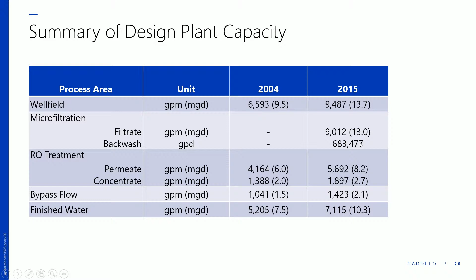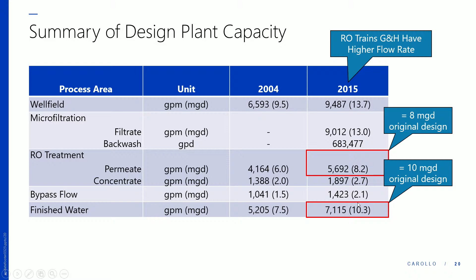And instead of a 10 million gallon per day nameplate capacity, it should actually be capable of producing 10.3 million gallons per day. But to get to that, we need 13 million gallons per day of filtrate from the microfiltration process and upwards of 13.7 million gallons per day from the well field. So as we walk through the rest of the presentation, we're going to look at how these various steps fall short in meeting those needs, in particular microfiltration, the well field, and the amount of water that we can bypass around the RO system.